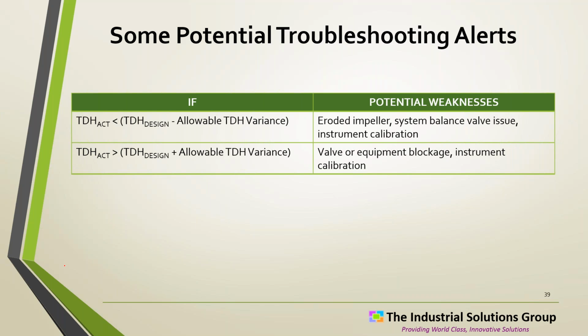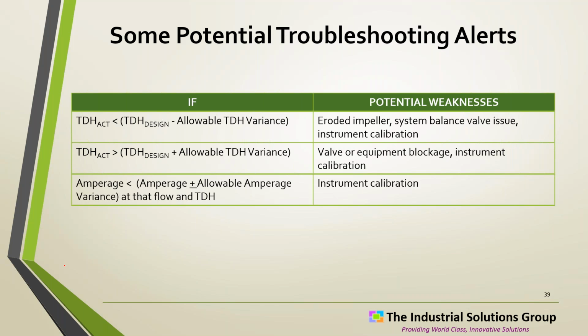You can flip it around the other way. What if the TDH is too high? Well, it could be a valve or equipment blockage. It could be an instrument calibration issue. Again, it's pretty easy then to start programming troubleshooting tips into the system once we have just a little bit of knowledge. Do the same thing with amperage, cross-checking flow meters, TDH, and it's an important measurement to make sure that our instruments are calibrated, and we can start flagging a calibration issue.